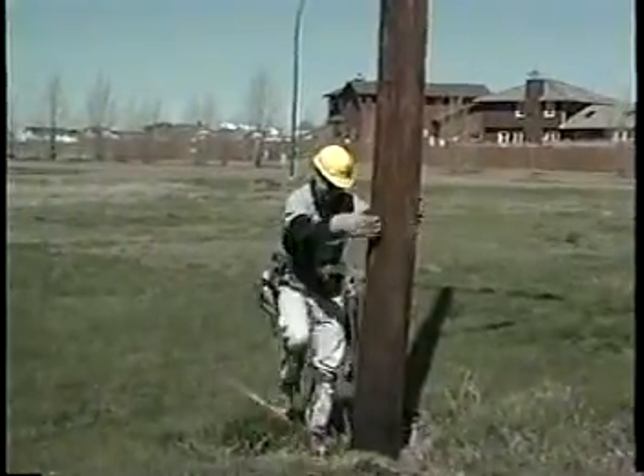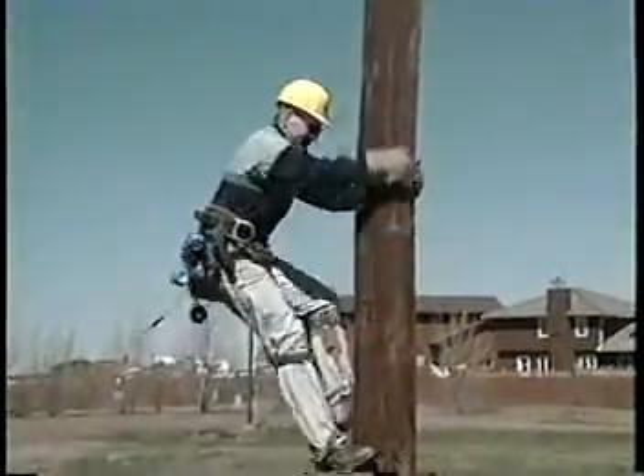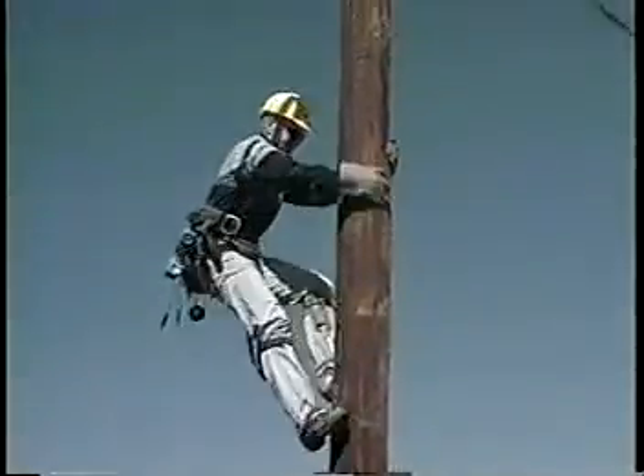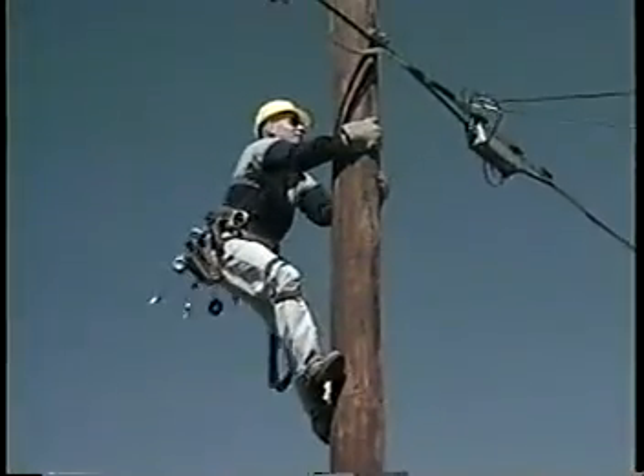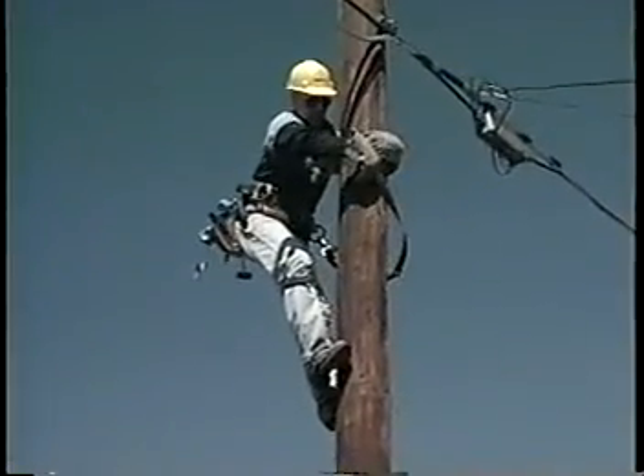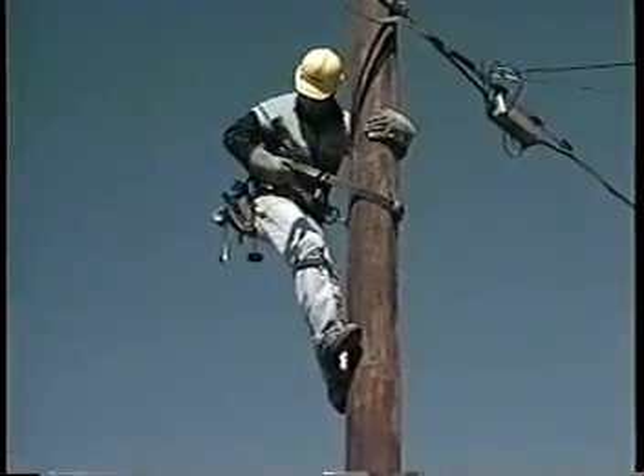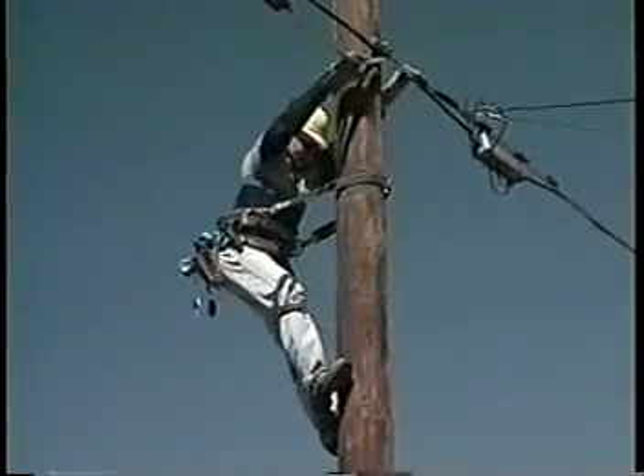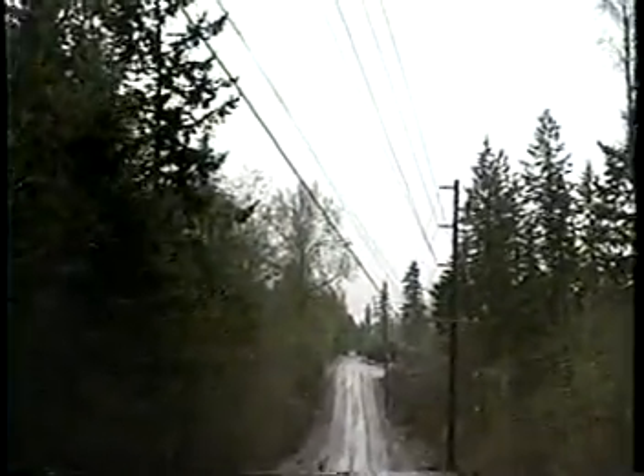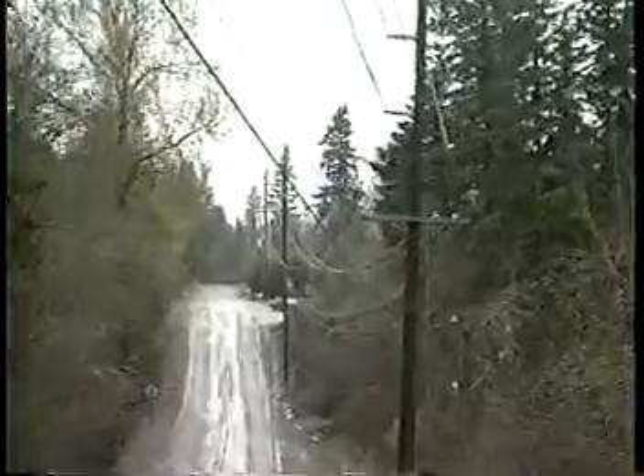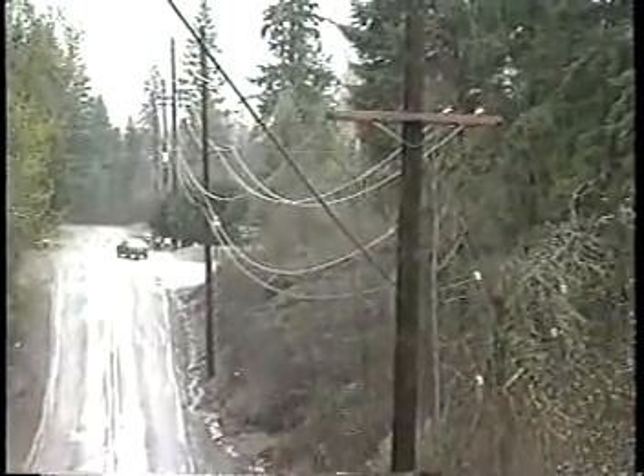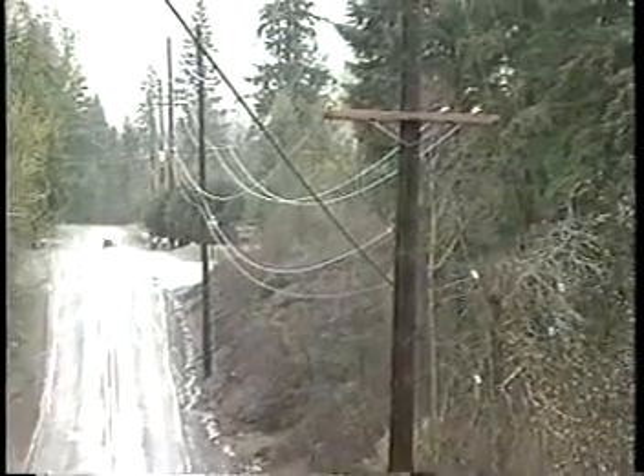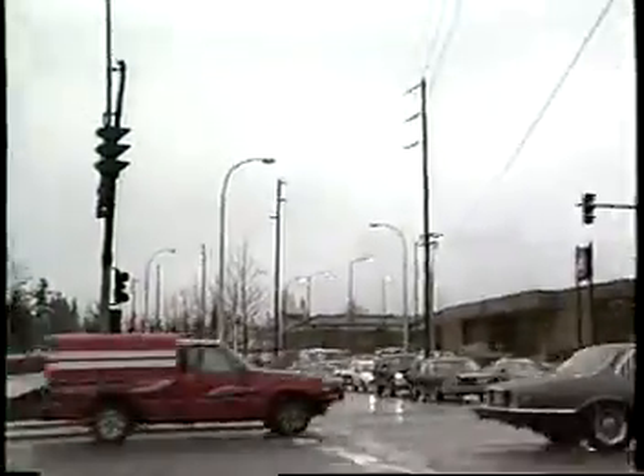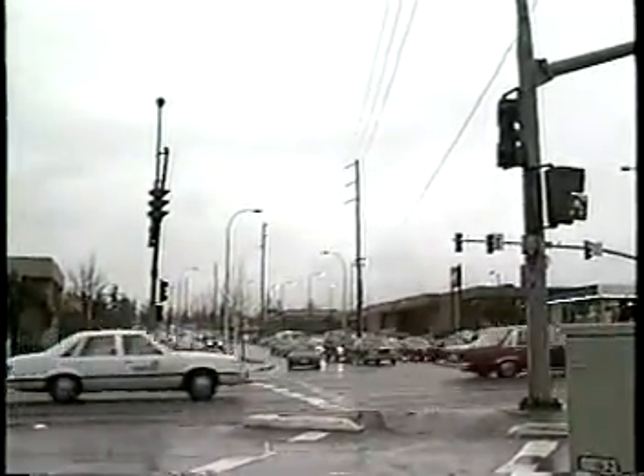Occupational health and safety codes provide for absolute limits of approach to aerial power lines. These distances depend on the level of voltage in the lines and range from 3 to 5 meters. Even when an aerial cable is installed between poles not carrying high voltage lines, shock danger may still exist. Long lengths of cable may build up lethal amounts of static electricity that will discharge through a person attempting to work on it. To prevent this, grounding clamps should connect the cable exterior with a good solid ground at each pole site. Metallic messengers must also be grounded in this manner. This will also better protect the cable from possible lightning damage.